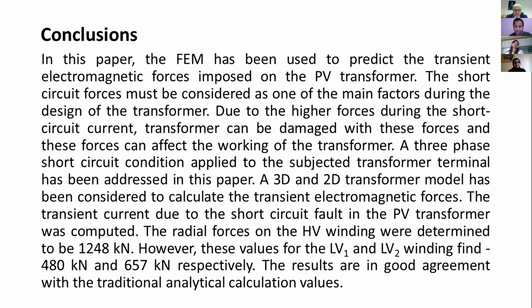A three-phase short circuit condition applied to the subjected transformer terminal has been addressed in this paper. A 3D and 2D transformer model has been considered to calculate the transient electromagnetic forces. The transient current due to the short circuit fault in the PV transformer was computed, and the results are in good agreement with the traditional analytical calculation values.